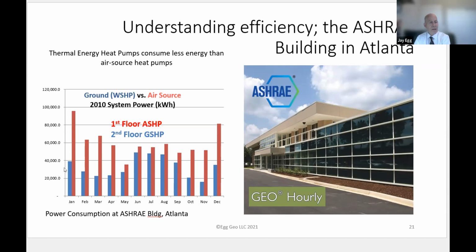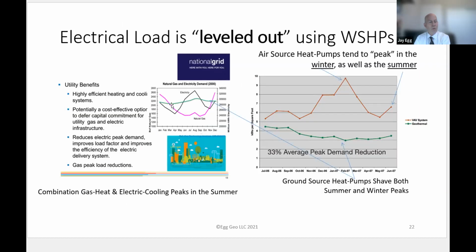And they found that the air source heat pumps, as we see this worldwide, require a lot more peak energy in the wintertime. And that's just because it gets cold outside. And in the summertime, they require more energy too, where the geothermal heat pumps have a much more stable energy consumption. Why? Because they're using the stable underground temperature. We can see this over and over again, as in this building comparison of two identical buildings in Oklahoma, US. The air source heat pumps in the middle of the winter peak dramatically, while the geothermal heat pumps are very stable.